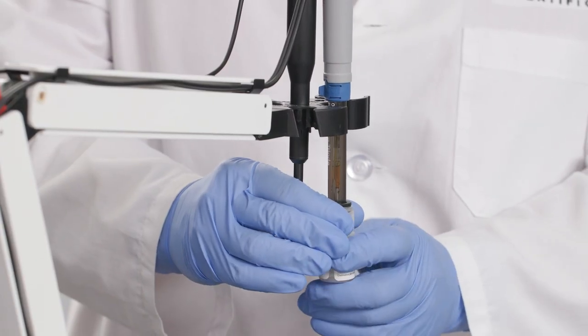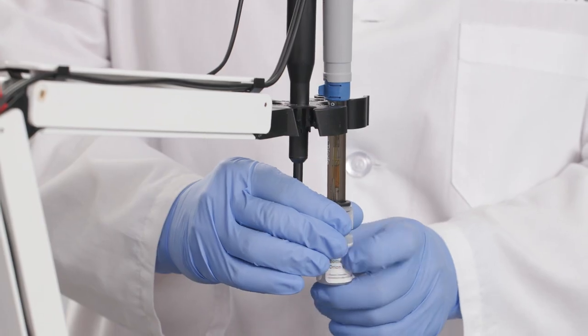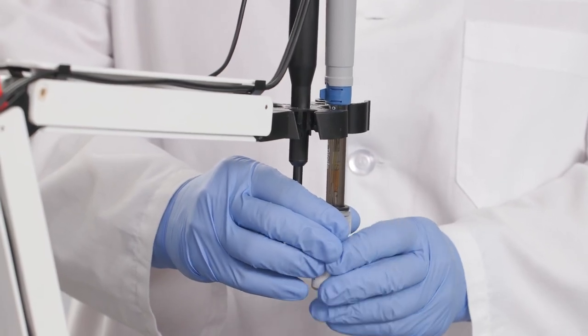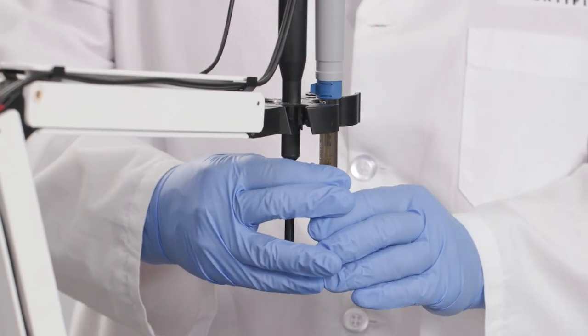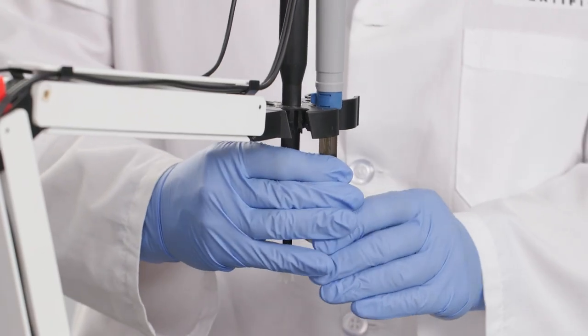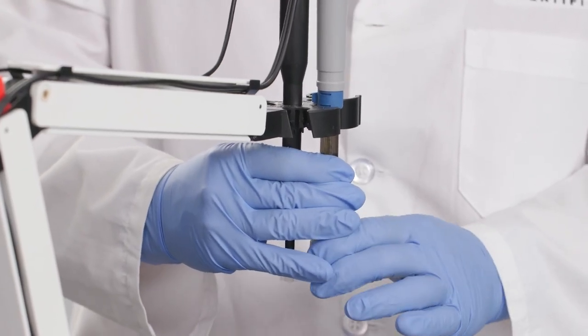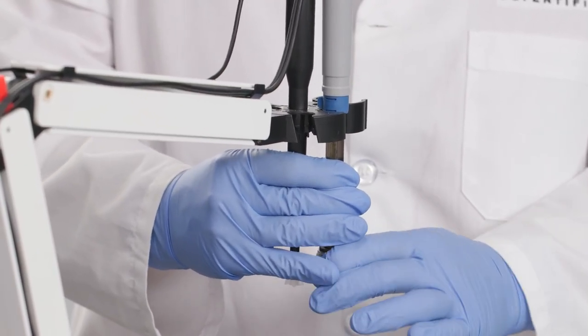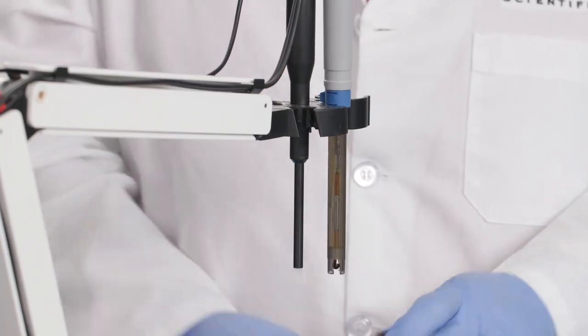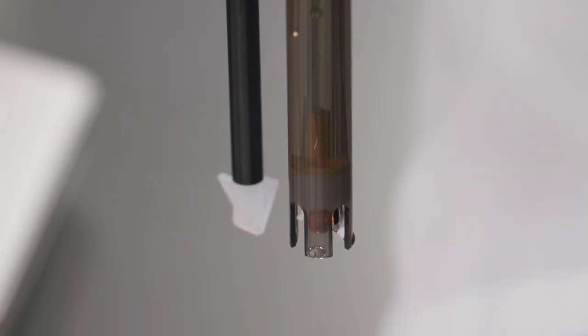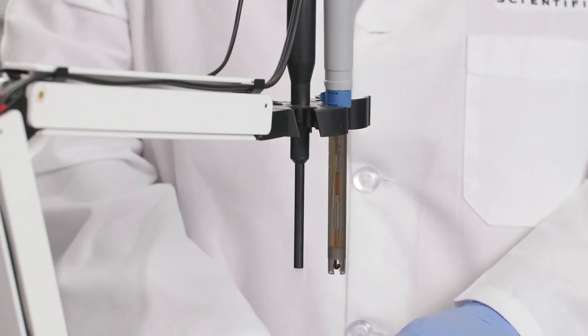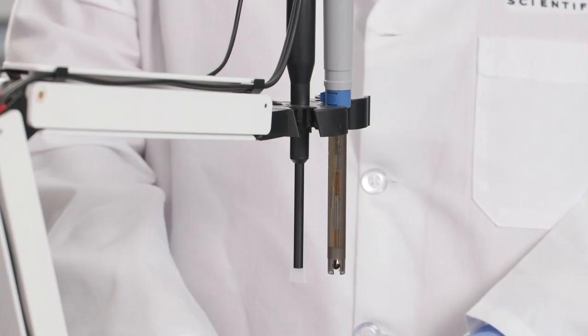Now, let's prepare the pH electrode. First, remove the electrode from the storage bottle by unscrewing the top. Then, remove the bottle and the cap. This helps prevent a vacuum that can pull fill solution from the electrode. Notice that the fill solution in the electrode and the storage solution in the bottle have not formed crystals or become dried out. This means that the electrode has been properly stored.